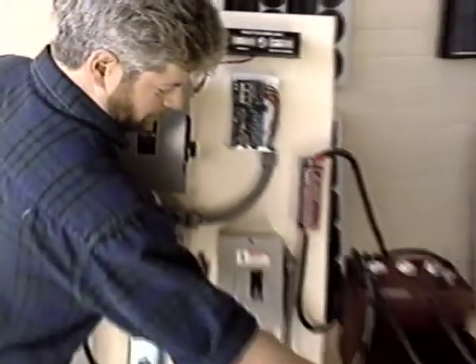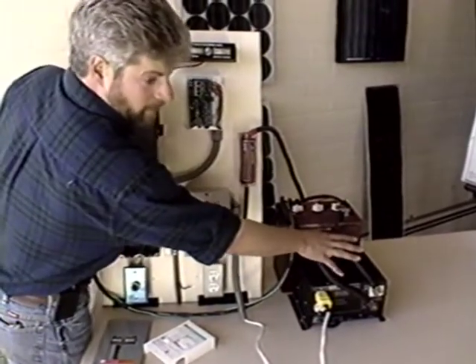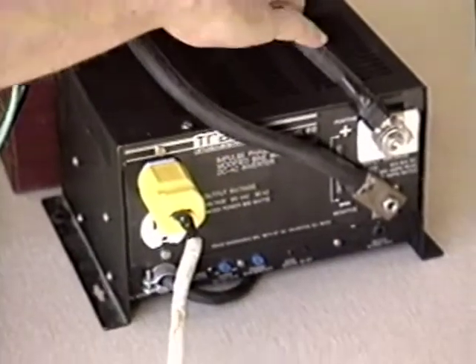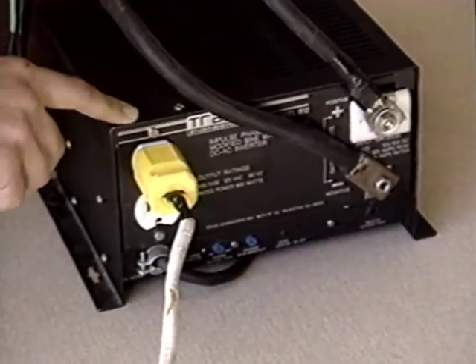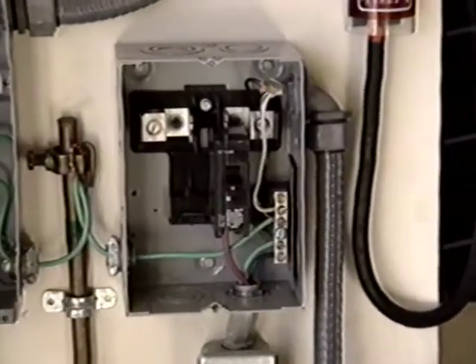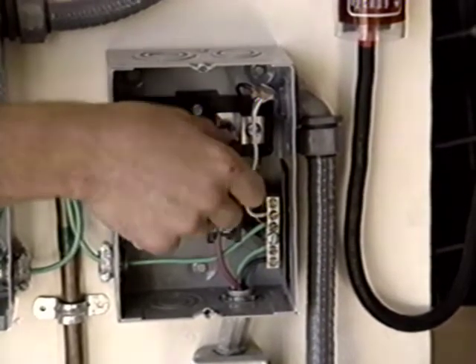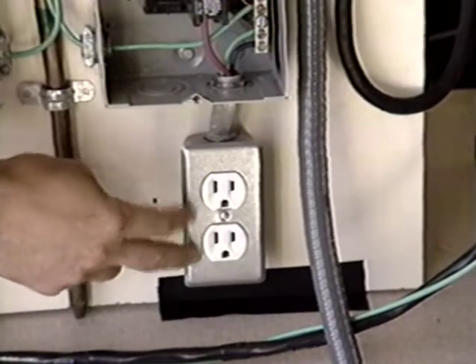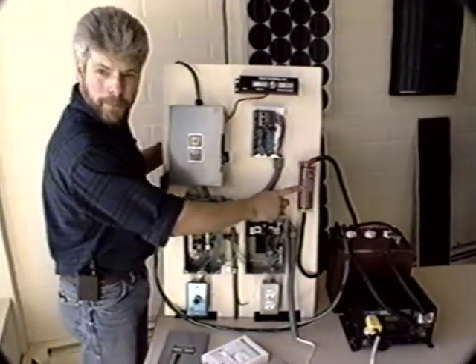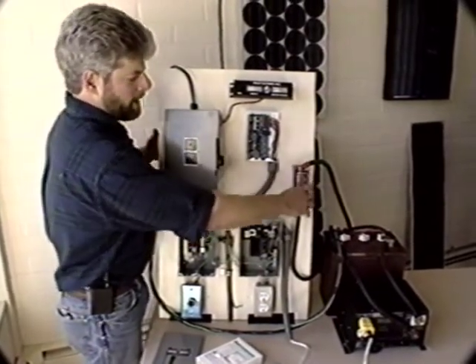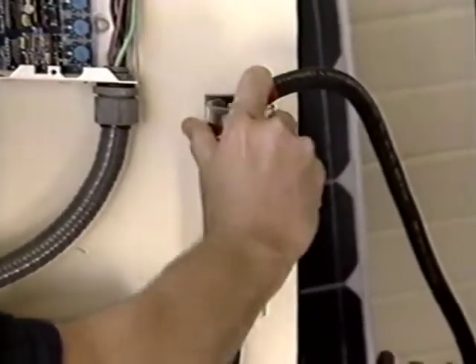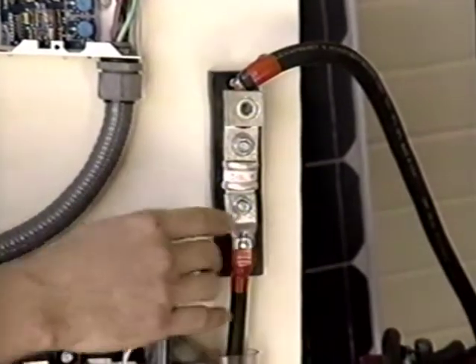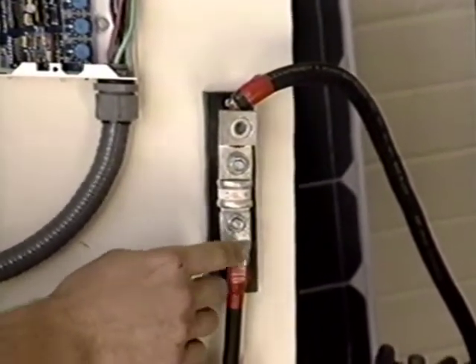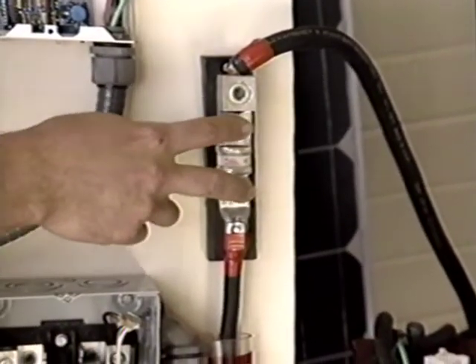The alternating current, the AC power, has to come out of the inverter. The inverter gets its power, 12-volt DC power, coming out of the battery, going into the inverter, being changed to 120 volts AC, and goes out to another AC load center in this case. And the AC load center is circuit breaker and fuse protection for the AC loads symbolized by this conventional AC outlet down here. The other piece of equipment you see here is a fuse, an inline fuse with a protective plastic cover on it. And we fuse the positive wire coming between the battery and the inverter, once again to provide overcurrent protection.